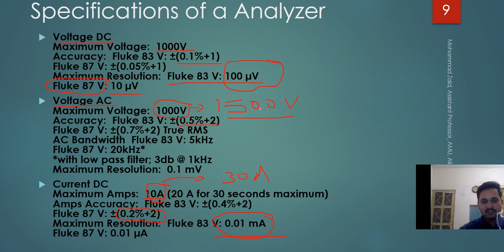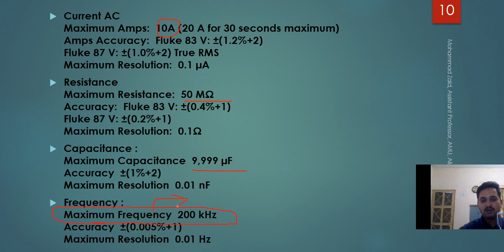Okay, then current is also 10 amperes for this make. Then resistance, maximum resistance is 50 mega ohm. Then capacitance is this. Frequency, maximum frequency, very important. Why is frequency important? Because you are going to measure harmonics, and harmonics have frequency which is many times the fundamental one.